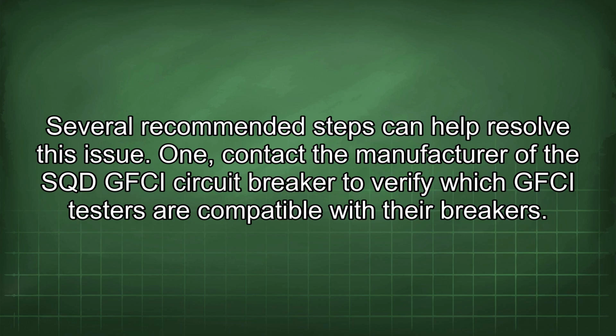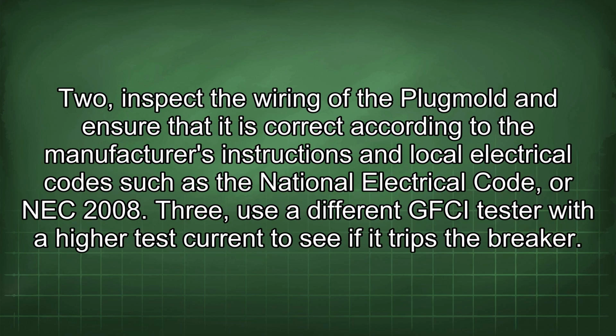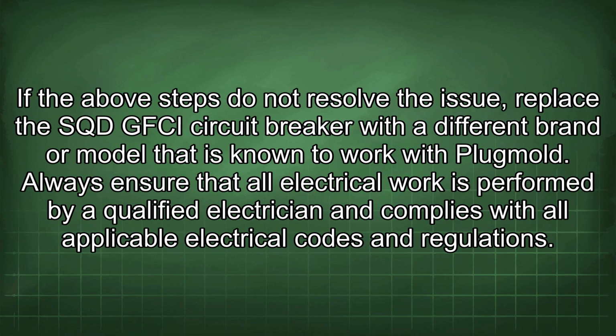1. Contact the manufacturer of the SQD GFCI circuit breaker to verify which GFCI testers are compatible with their breakers. 2. Inspect the wiring of the Plugmold and ensure that it is correct according to the manufacturer's instructions and local electrical codes such as the National Electrical Code, or NEC 2008. 3. Use a different GFCI tester with a higher test current to see if it trips the breaker. If the above steps do not resolve the issue, replace the SQD GFCI circuit breaker with a different brand or model that is known to work with Plugmold.